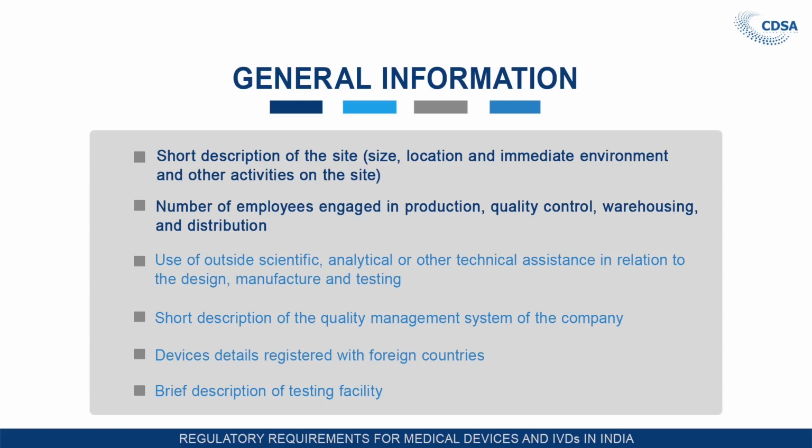Use of outside scientific, analytical or other technical assistance in relation to design, manufacturing and testing. Now, this is also very important because this also gives references to technical personnel. If you test the product in your own laboratory, you should have technical personnel appropriate to the testing of that particular medical device in your own laboratory. If you test it outside, if you take outside technical assistance, then that has also been mentioned, and that outside technical assistance, which is a laboratory basically, should also have technical personnel appropriate for testing that particular medical device.